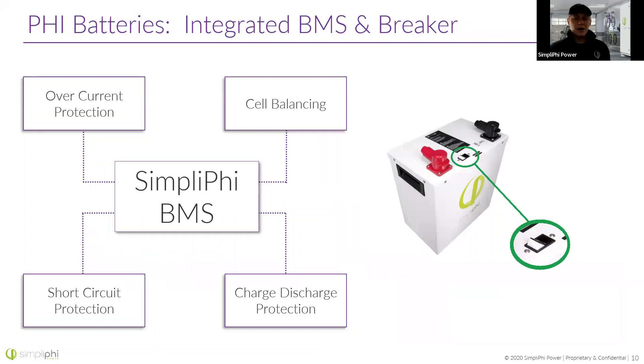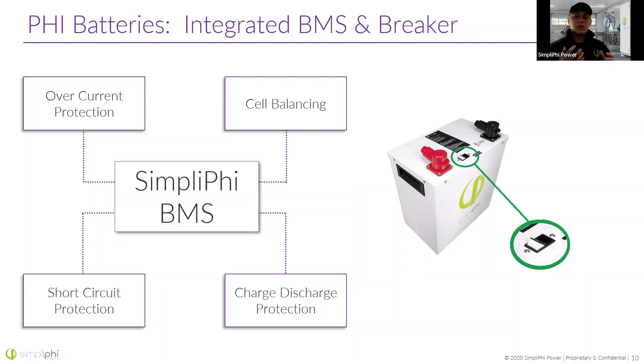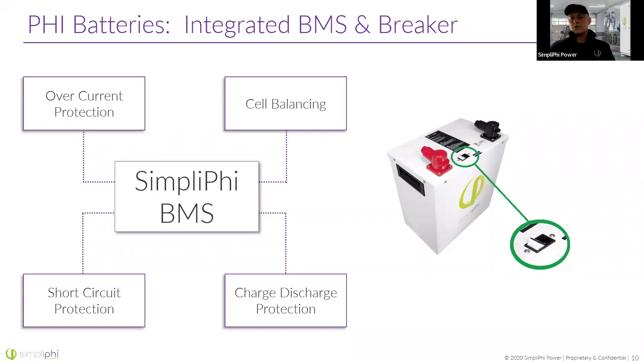We also have an integrated BMS internal to the batteries and a circuit breaker on top. The BMS handles overcurrent protection, short circuit protection, charge and discharge over- and under-voltage, and most importantly, cell balancing. The breaker on top adds additional overcurrent protection, but it's also a really handy feature for installing — especially in mobile systems where you don't have a lot of space. You're working in a tight space and it can be really nice to just turn that battery off while you're installing it so no sparks fly, then simply turn it back on once everything is wired up.